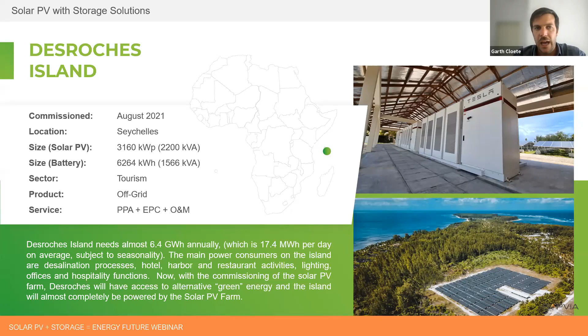Starting off with off-grid applications: at SBS, we're fortunate to have done quite a few off-grid type systems, and this is one example. We've got an island out in the Seychelles where we've built a 3 megawatt peak solar PV plant plus 6 megawatt hours of battery storage. With that battery storage and solar PV, we're creating an off-grid environment that reduces reliance on diesel. Any remote site has very high costs of getting diesel to the facility, with barge costs, trucking costs, and all the logistics, so any form of renewable generation makes an impact.